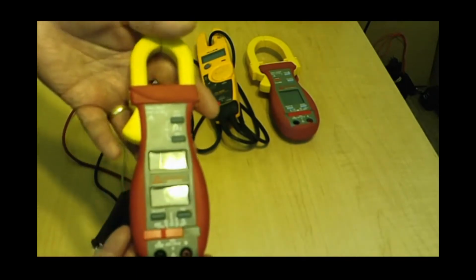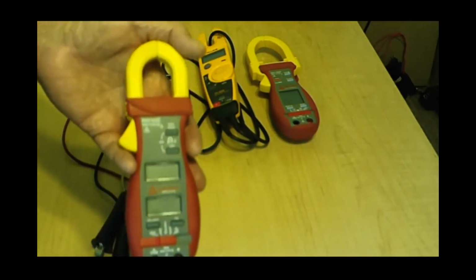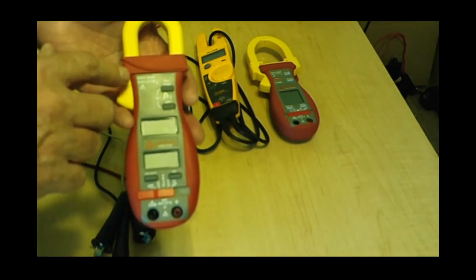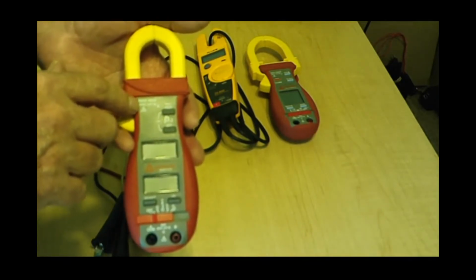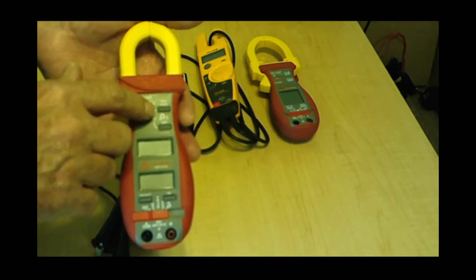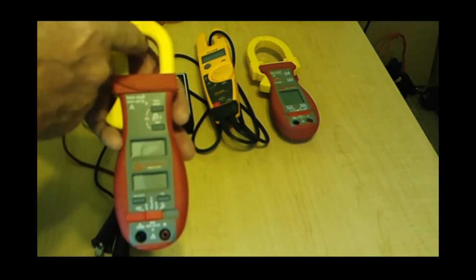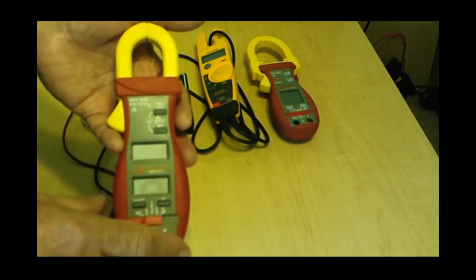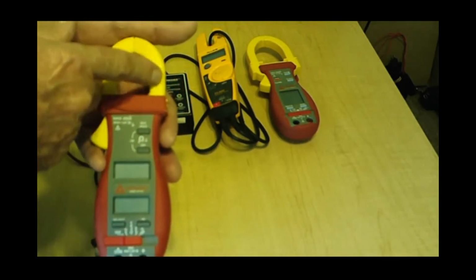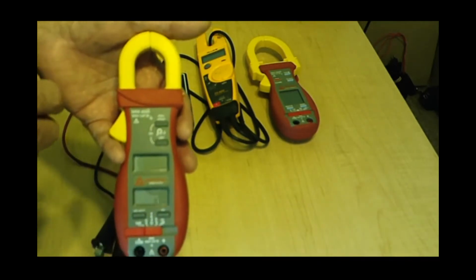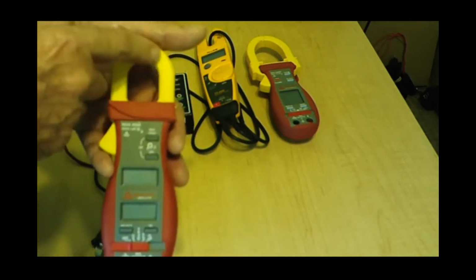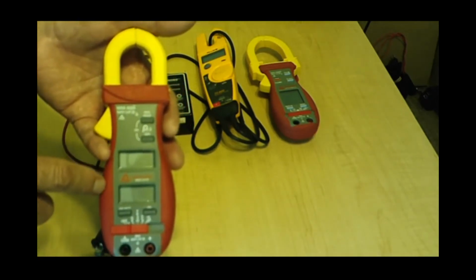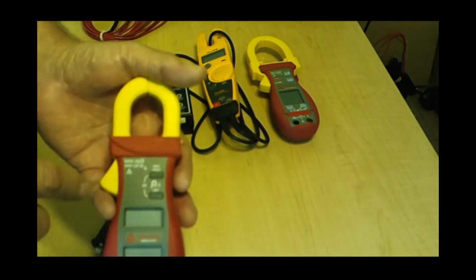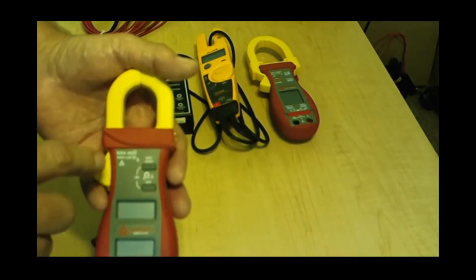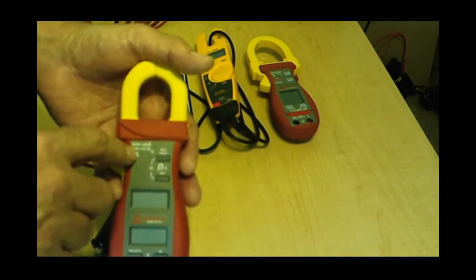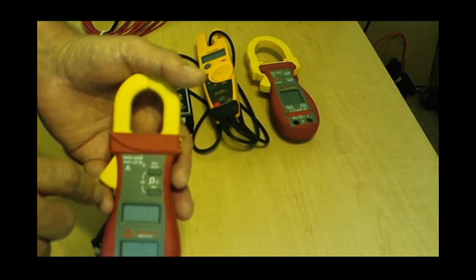We take this common meter. It's a clamp-on amp meter. This is an amp probe. There's all kinds of these out there. Right here, the current says maximum 400 amps, 600 volts, Cat 3. Well, this little clamp right here can read no more than 400 amps. If you go above 400 amps, one, the wire's not going to fit, and two, if you do get it to fit, it'll probably cause this meter to actually catch fire and burn. It will not explode, but it'll catch fire and burn. Now, that's 600 volts, so 600 volts at 400 amps.